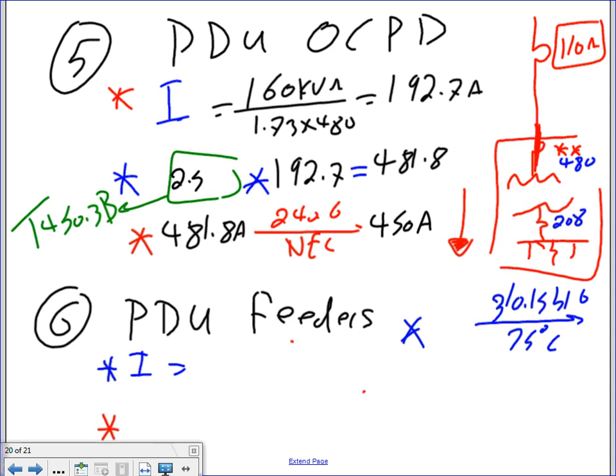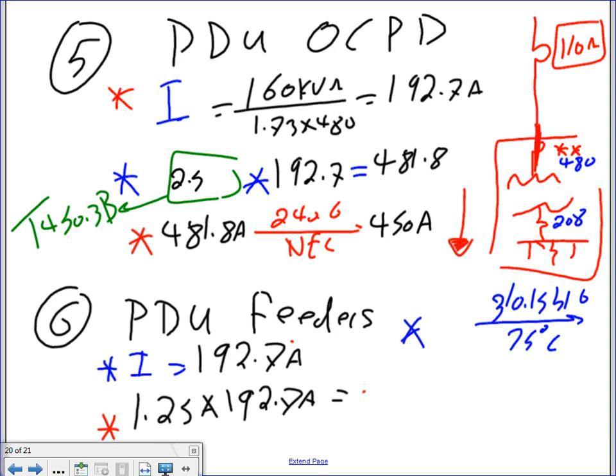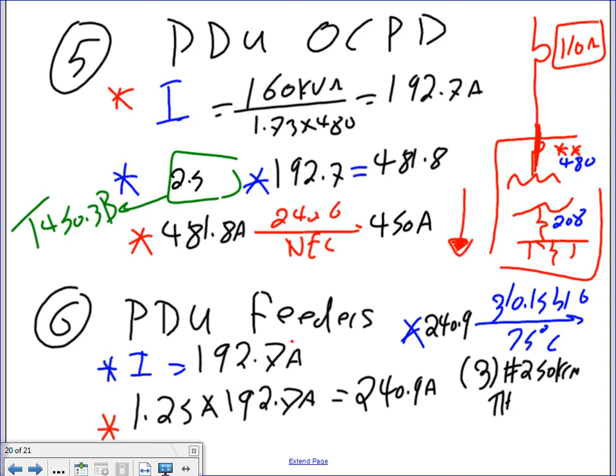Okay, the conductors. The conductor size, guys: you multiply 1.25 times 192.7 amps. What do you guys come up with here? How much? 240.9 amps. And then you're going to take the 240.9 to, did we size this, didn't we? So what do you come up with? 250. Yeah. How many conductors? 3 conductors still. Number 250 kcmil THHN. So that's the conductor coming to the PDU. That's this one here. That's 3 conductors. What did they say? 250 kcmil.